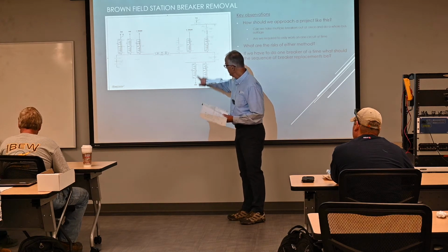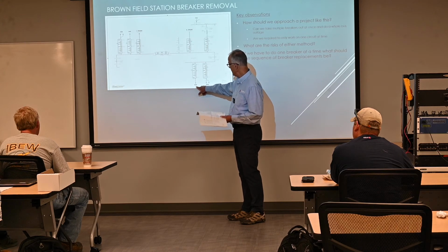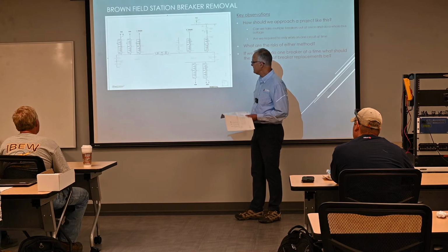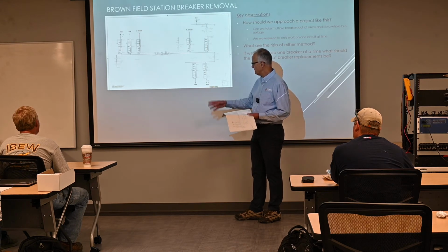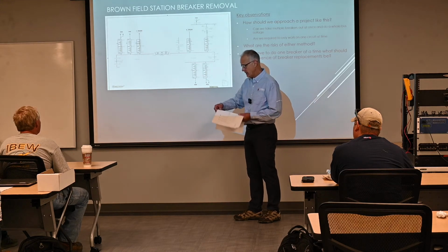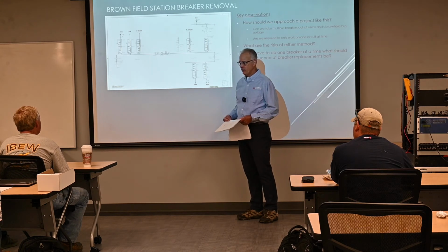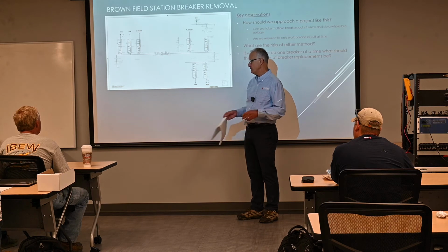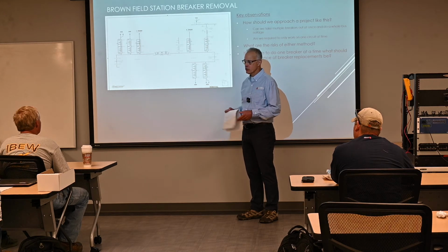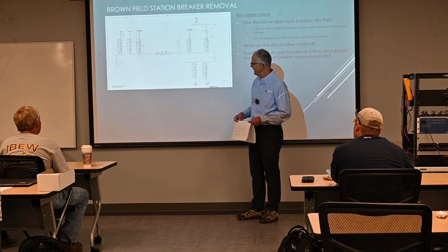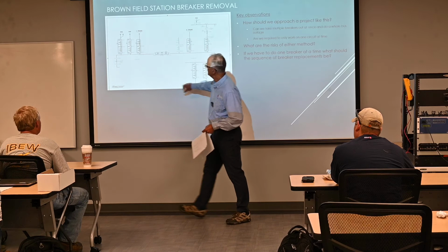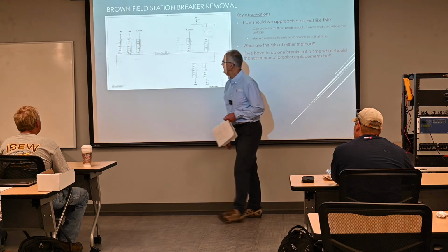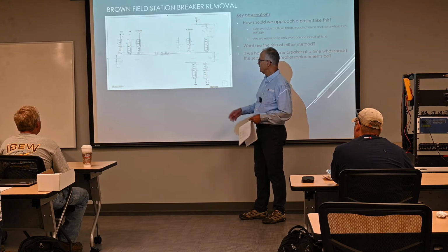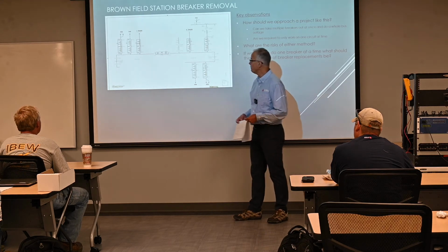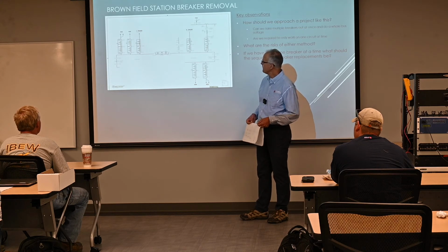So this is a transmission line. This 668 line has no number underneath it, no lines, so that tells me that's a distribution circuit. It's going to customers' stations. Whoever's taking 11 kV circuits, usually 11 kV circuits in Rochester feed larger businesses that have maybe one or two sources, and they'll have a throwover switchgear there. And maybe customers being fed from 668 and this circuit over here, 545. They would never let you take both buses out at the same time or both circuits out at the same time. What else is interesting in here?